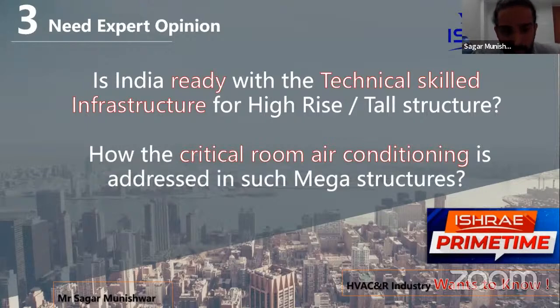We require a chiller that can operate at a higher operating pressure. A general chiller data sheet comes with an operating pressure of say 10 bar, but for a high-rise building you need a chiller selection that can operate at higher pressure. Do we have those kinds of systems in India? The answer is yes.